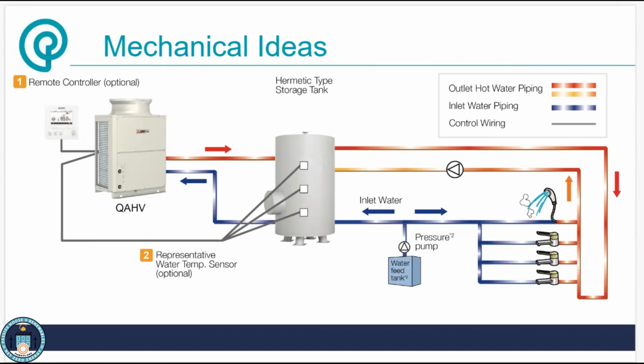And then this is very comparable in efficiency. In fact, for heating, the CO2 is significantly more efficient than a traditional R410A might be. So for example, a typical heat pump doing space heating might make about a COP of 4 at 47 degrees, somewhere in the 2 to 2.5 range at 17 degrees, and about 1 at 5 degrees Fahrenheit. A CO2 water heater at 45 degrees will have a COP in the 5s, and then they're able to maintain a COP of about 2.5 down to minus 40 degrees Fahrenheit. So their efficiency curve is spread out much wider, and they're much more efficient at heating that water.